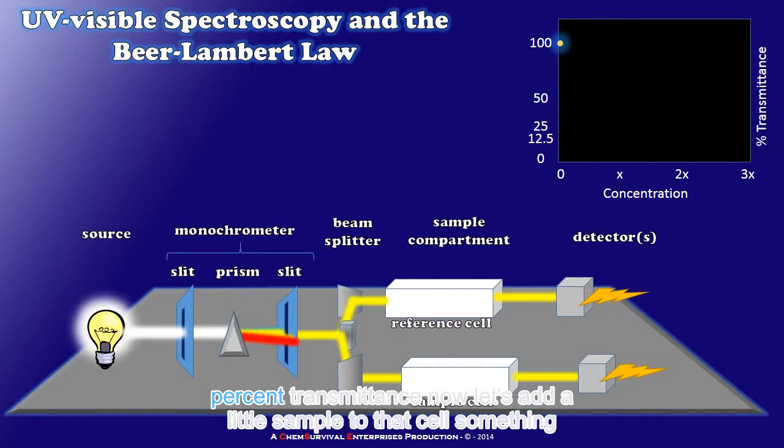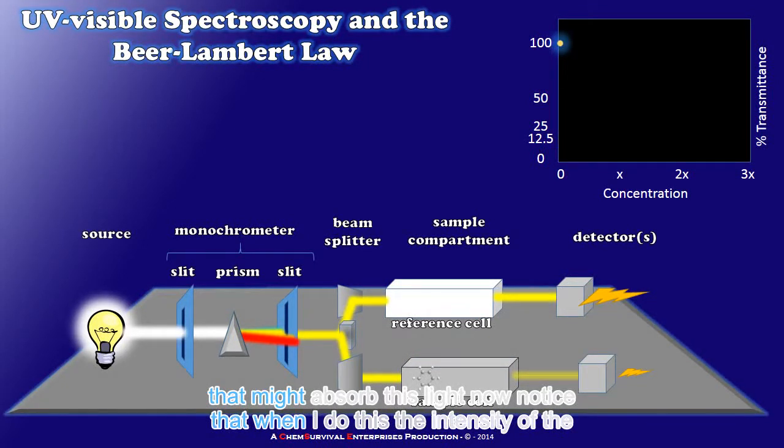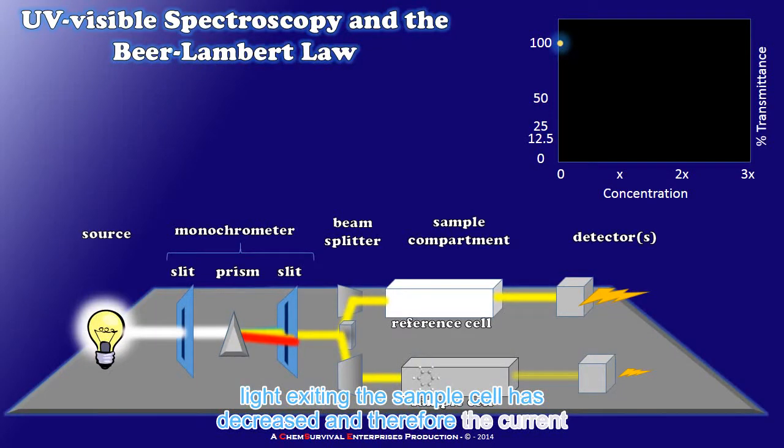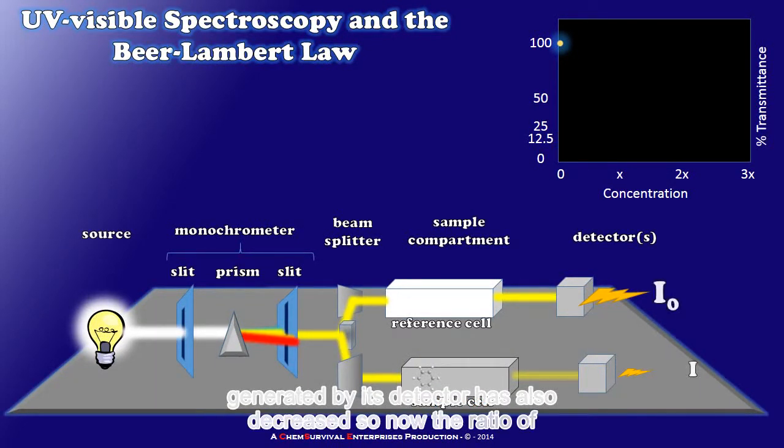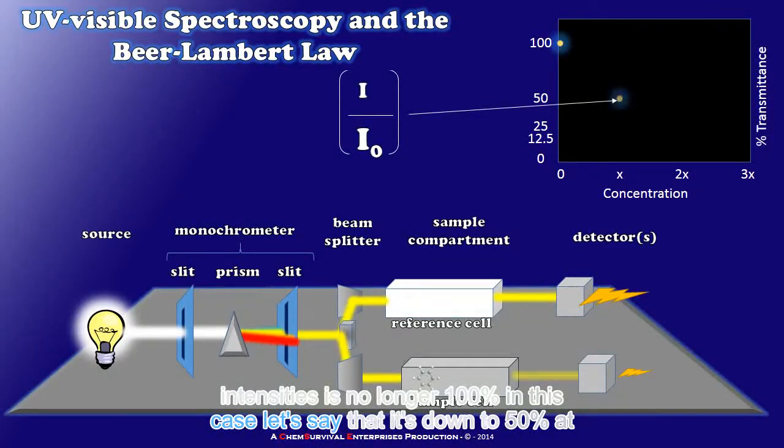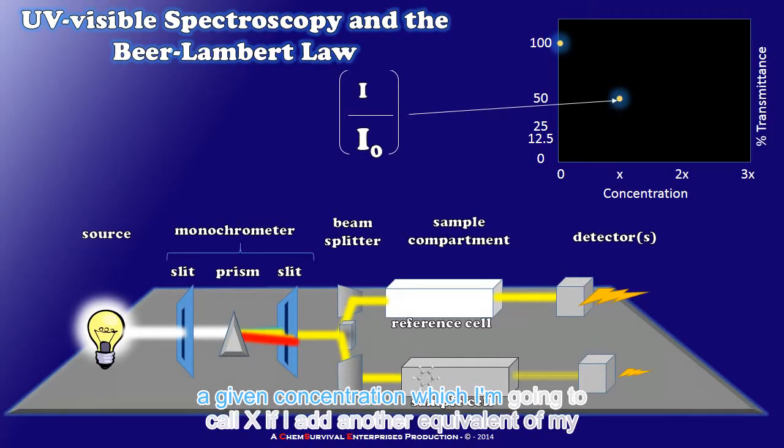Now let's add a little sample to that cell, something that might absorb this light. Notice that when I do this the intensity of the light exiting the sample cell has decreased and therefore the current generated by its detector has also decreased. So now the ratio of intensities is no longer 100%. In this case let's say that it's down to 50% at a given concentration which I'm going to call X.